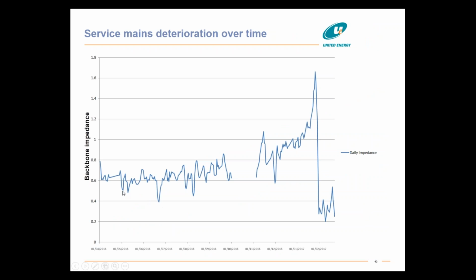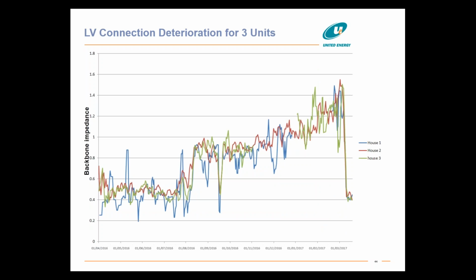We've also noticed that if we look at impedance on the Y scale, it sometimes creeps up over time—this is over a 9 month period. We can see the network impedance got worse, we fixed it, and afterward it settled back to about 0.3 ohms. So in some cases this was a good indication that problems aren't always sudden; we can pick them up over time and start to plan for it.